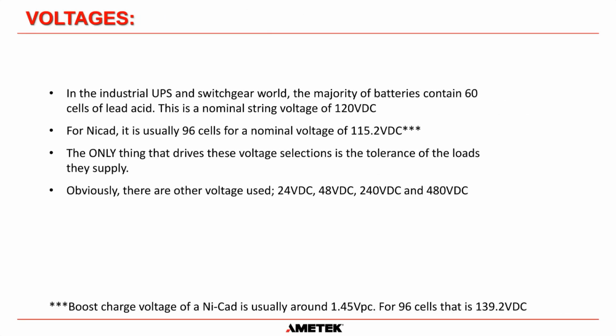In the industrial UPS and switchgear world, which is pretty much the world that AMETEK Solidstate Controls lives in, the majority of batteries contain 60 cells of lead acid. So that would be a nominal string voltage of 120 volts DC. For a NiCad battery, that would be usually around 96 cells, and that would give you 115.2 volts nominal voltage.